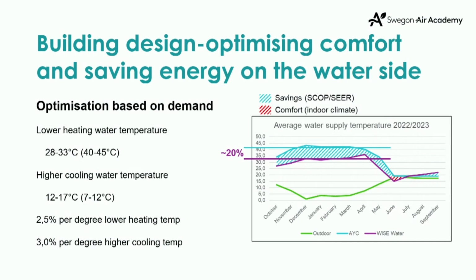And also, if you look at the graphs, for each month, you have the average temperature that has been produced. And as you can see, instead of working with the design temperatures of 40 to 45 degrees in heating, we are working with 28 to 33. And the same goes for cooling. So instead of 7-12, we are working with 12 to 17. And this is where we save a lot of energy. Yeah. So a huge opportunity in savings on the water side. That's maybe a more hidden system part than we normally look at in the HVAC system.